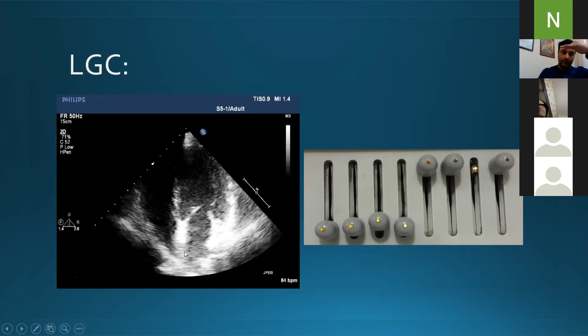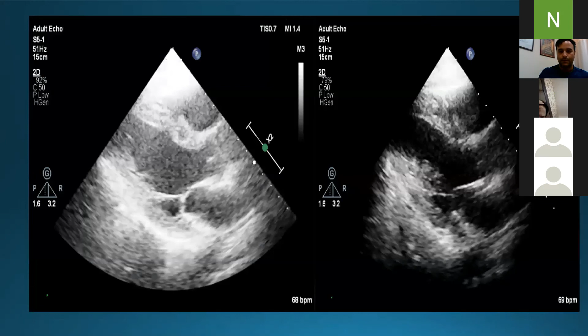And in the machines which we purchase now, in the last 4 or 5 years, we don't have to worry about the gain control, because there's a button there, iScan, auto scan. Like here, I'll show you. This iScan. You have to press on this button. The machine will automatically select appropriate gain and appropriate compression, appropriate zooming, and appropriate depth. It will itself select the appropriate parameters. You don't have to worry about that. But just remember, compression gain should be around 50. This TGC and LGC. TGC is for the horizontal sweep, and LGC is for the vertical sweep. Whichever area you want to make brighter, whichever area you want to focus on.